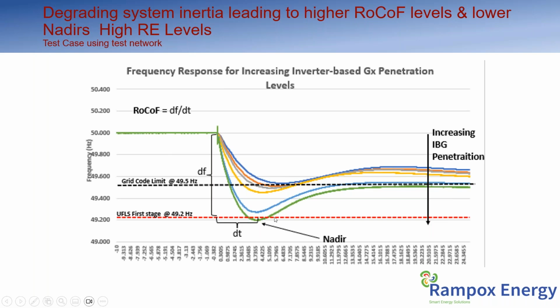We had done several studies showing that the last one was around 60% penetration in the South African system. A similar model we networked for the South African system showed that at around 60% penetration — not 60% as in installed capacity, but 60% instantaneous penetration — sometimes even your 20% installed capacity can easily become 60% during certain loading conditions, because now we are not talking about installed capacity.